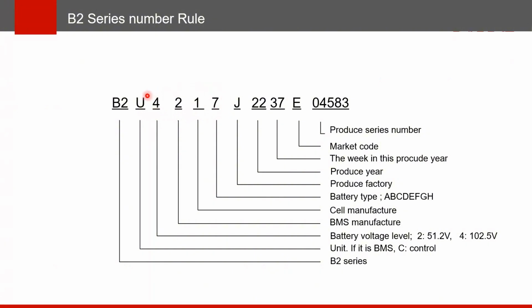And these four figures we need to pay attention to because they represent different battery levels or different battery types. Some installers may make mistakes when they pick up the batteries from the warehouse. They may bring other figures like 4, 2, 1, and this 5, or this 5-0. These different figures represent different types of batteries, and different types of batteries can't be installed in one tower. Remember this. So we need to make sure the battery types are the same in one tower. Okay, so let's go on.